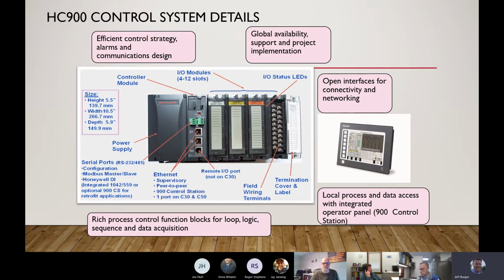The other thing that makes it really nice when you replace these I/O cards is that the terminal block on the very front here has a top screw and bottom screw. You can leave all your wiring left on the card, and then all you have to do is remove these 2 screws, remove this terminal block, and then pull your card out, put the new card in, and then replace the terminal block. This saves a lot of time, a lot of downtime, because you don't have to worry about rewiring the card when you put a new one in.